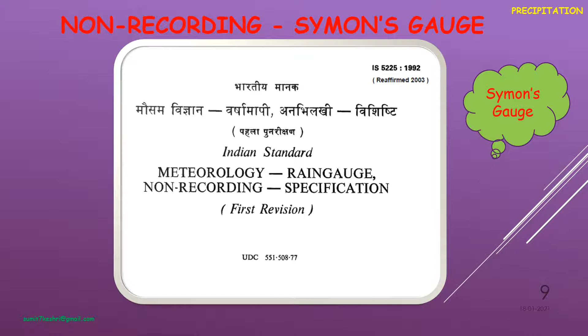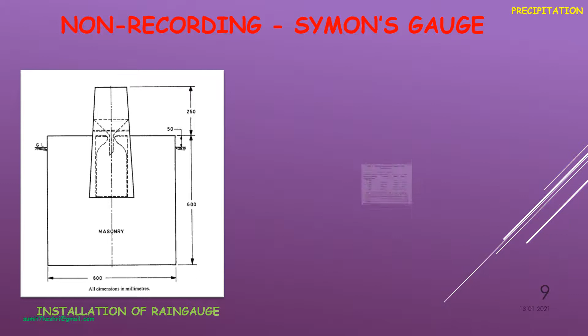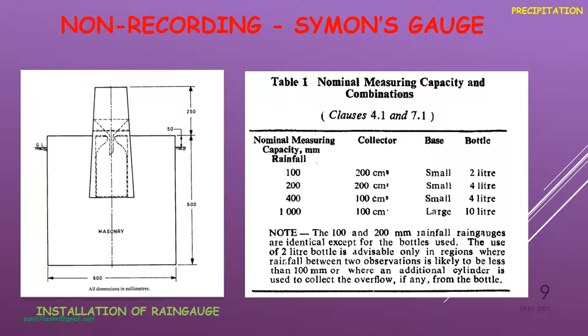The rain gauge consists essentially of a collector which intercepts the sample of rainfall to be measured and a receiver consisting of a base and a bottle in which the rainfall collected is stored. The collector is exposed above ground level while the receiver is fixed partially below ground level. This standard specifies two collectors 200 cm square and 100 cm square in area, 2 bases and 3 bottles of capacity 2, 4 and 10 liters. All components are completely interchangeable and combinations of these provide the rain gauge as given in table 1 of Indian Standard 5225.